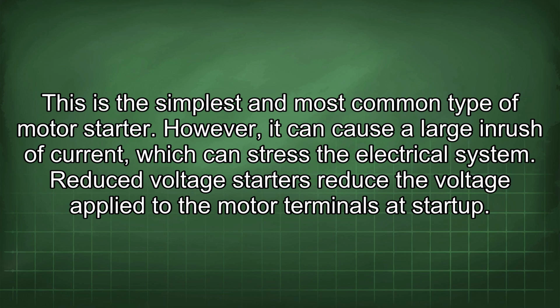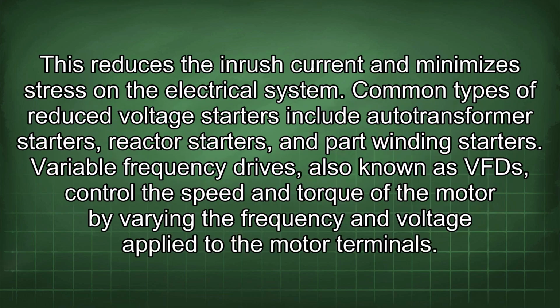Reduced voltage starters reduce the voltage applied to the motor terminals at startup. This reduces the inrush current and minimizes stress on the electrical system. Common types of reduced voltage starters include auto-transformer starters, reactor starters, and part-winding starters.